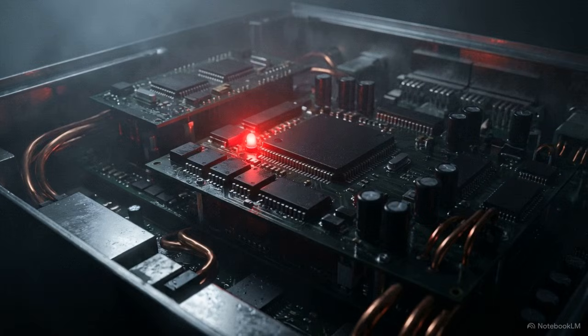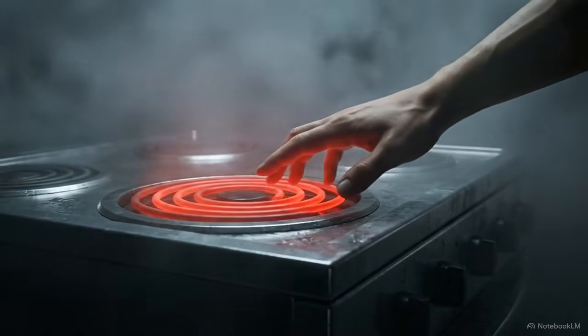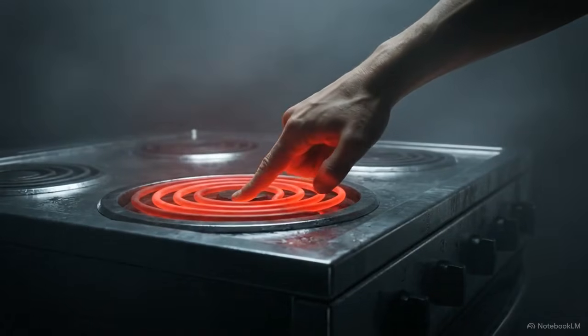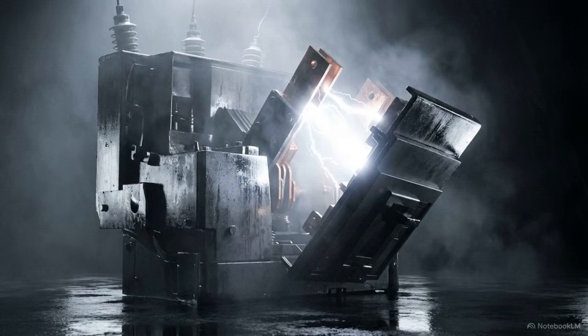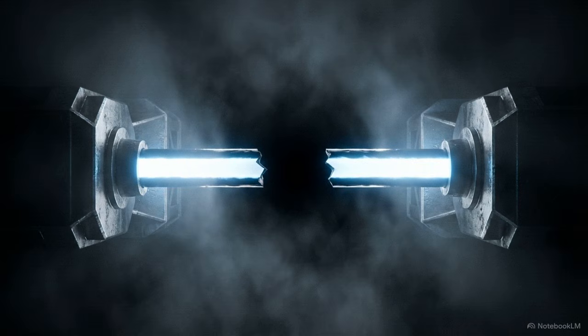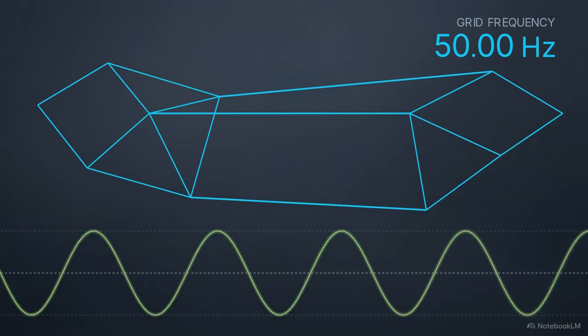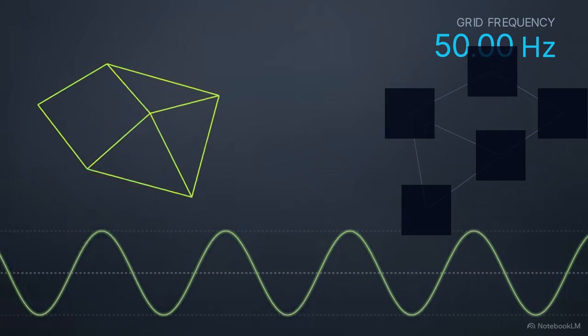These are decentralized digital brains that sample current and voltage hundreds of times a second to detect these exact anomalies. These relays act like a reflex arc, similar to the way your hand jerks away from a hot stove. Before a human could even blink, the relay sends a command that forces giant circuit breakers to physically trip, amputating the damaged section of the line in just 60 milliseconds. This self-amputation stops the surge, but severing a major power artery creates an immediate system-wide imbalance between supply and demand.